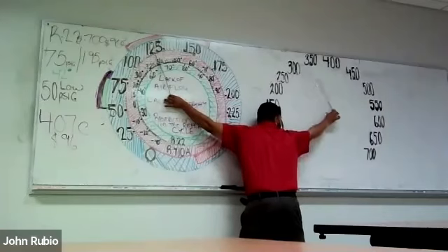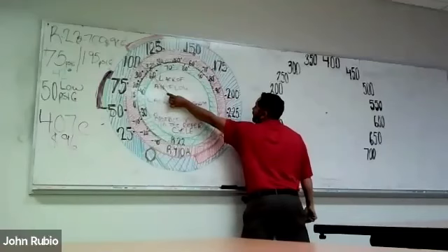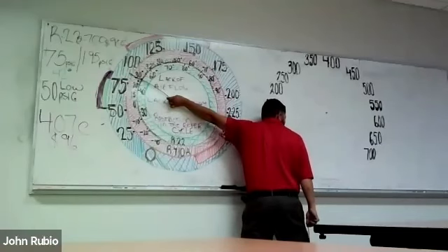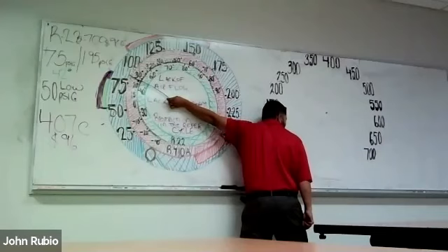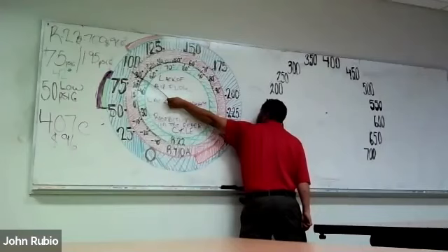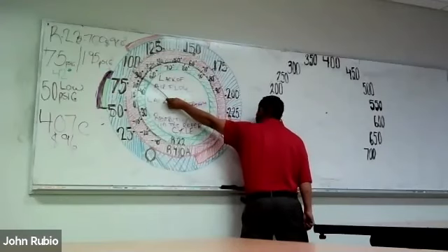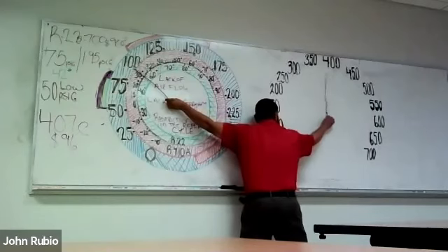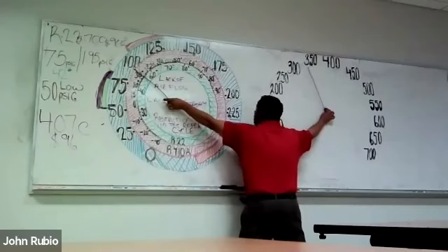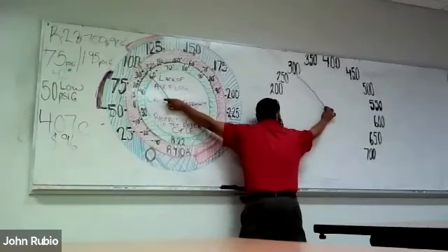If you don't have your high side connected and you walk up and you're sitting at 90 on 410A after your warm up, you are by all thinking, hey, I am low on refrigerant. But for some reason, when I try to add refrigerant, this moves up for a second and it looks like it takes it, but then it doesn't. Why? I keep trying to put gas in it, but it's low, but it won't take it. It's not low, it's restricted. But if you do not have your high side connected, you will not have the verification of congruency in the high side needle to tell you truly are low.